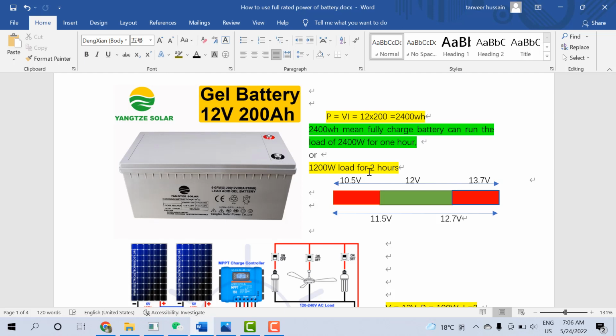What is the problem in this case? This is not a problem with your battery. If you have a new battery, or if the backup time suddenly drops, that's different from a gradual drop. If the backup duration drops slowly, you can say the battery life is decreasing, that's why the time is slow. But if it suddenly drops, or a new battery gives you less time, this means your installation has something wrong.